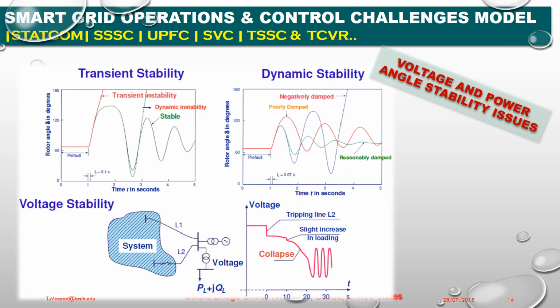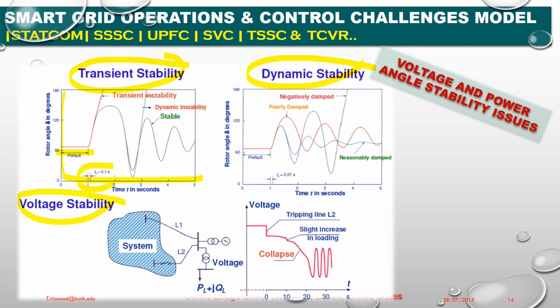Voltage and power angle stability issues. Now we are going to discuss transient stability, dynamic stability and voltage stability. First, what is transient stability? Transient stability is demonstrated in the graph of rotor angle versus time. This is my pre-fault condition, and this is where a 0.1 second fault was created, and the system was isolated and went out of phase. That is transient instability. Second, if you can see here, the green line has also gone out of phase. That is dynamic instability. After 3 seconds, the system was stabilized after implementing a solution, and the waves were damped out.